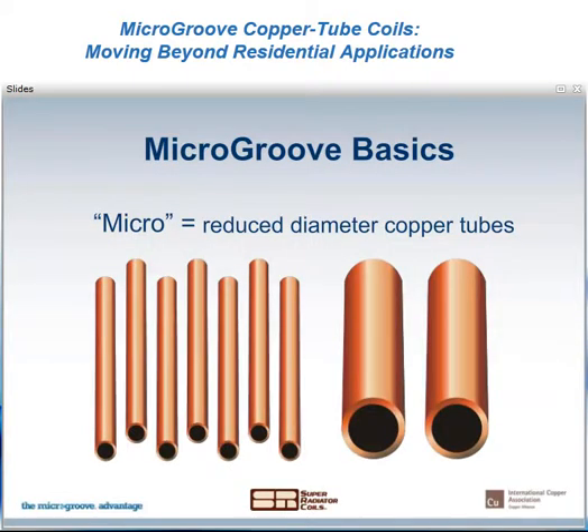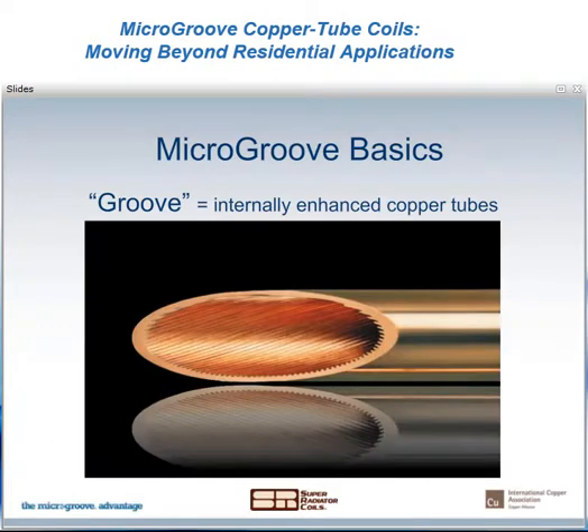Micro, in the word MicroGroove, refers to small diameter copper tubes. And as you can see, when we reduce tube diameters, the result is a big increase in surface area that's available to transfer heat. Groove, in the word MicroGroove, refers to enhancements that are found on the internal surface of the tubes. These enhancements are grooves or patterns that reduce boundary layers that form inside the tube. And we want to reduce or eliminate these boundary layers because they act as an insulator and they slow down the heat transfer that we really want to have happening as fast as possible.